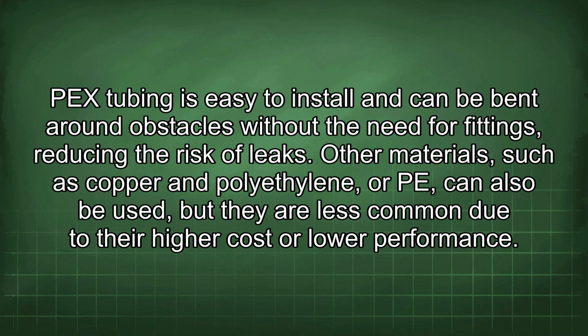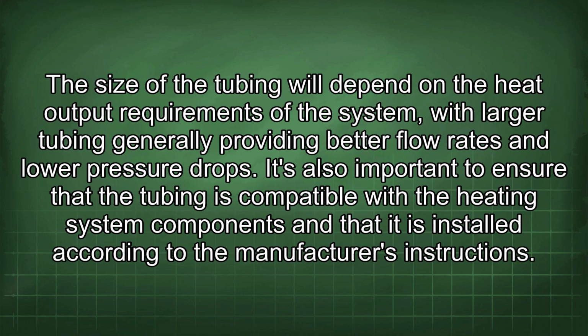PEX tubing is easy to install and can be bent around obstacles without the need for fittings, reducing the risk of leaks. Other materials, such as copper and polyethylene, or PE, can also be used, but they are less common due to their higher cost or lower performance. The size of the tubing will depend on the heat output requirements of the system, with larger tubing generally providing better flow rates and lower pressure drops. It's also important to ensure that the tubing is compatible with the heating system components and that it is installed according to the manufacturer's instructions.